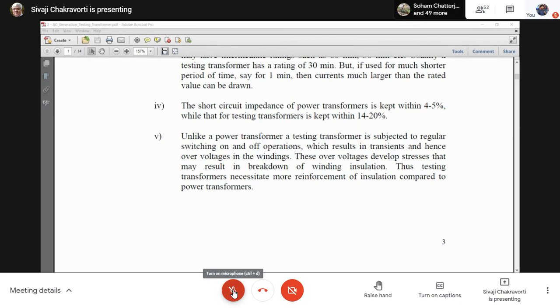Now, a power transformer is hardly switched on and off, very seldom. Once I switch on a power transformer, typically, if you have to switch off the transformer, a large area will be out of power, which means that to shut down a transformer, a lot of planning is required. And this is typically done maybe once or twice a year, just for maintenance purposes. So they have very little switching on and switching off, except of course the fault condition.